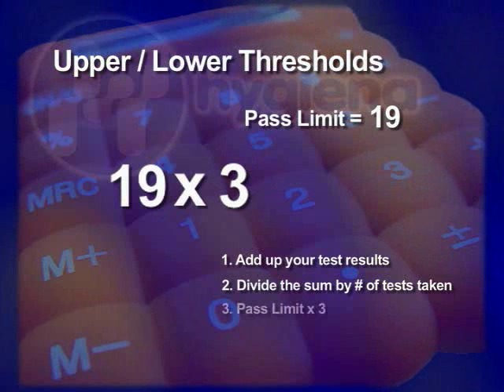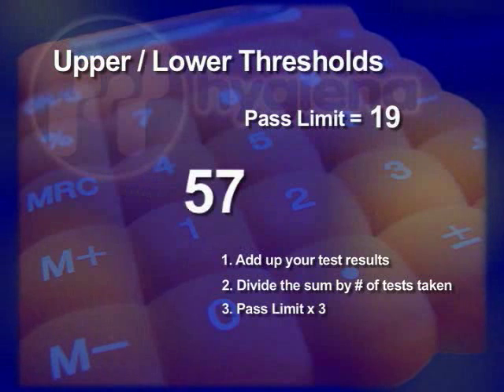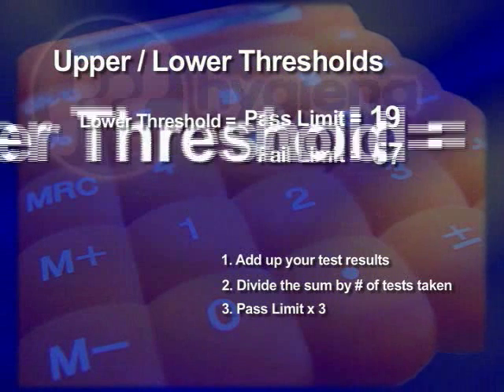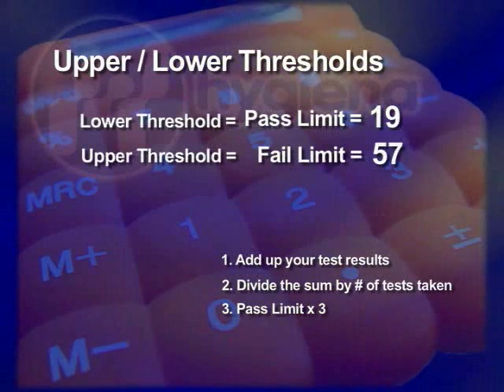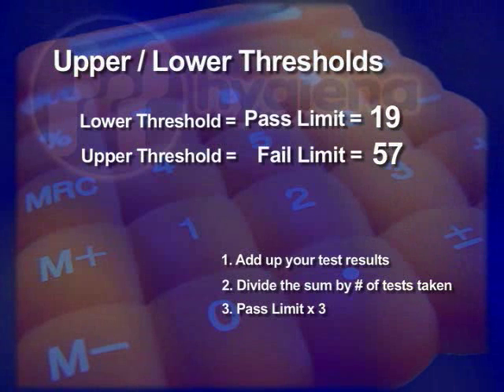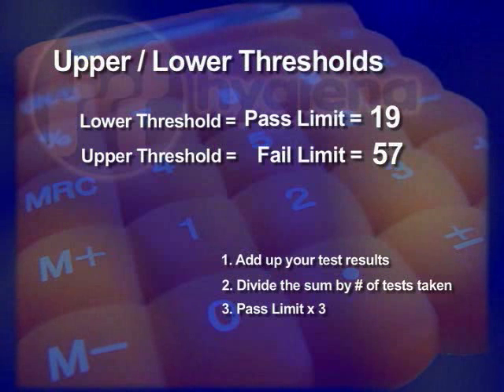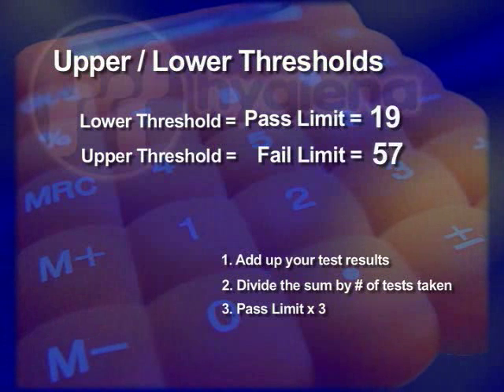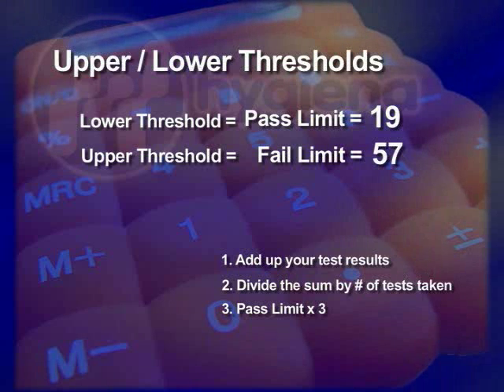Next, multiply your pass limit by 3. This will give you your fail limit. These are your thresholds. You can now enter them into your System Sure Plus program and synchronize to your device, or enter them directly into your Luminometer under the threshold category. Any test number falling in between these two numbers should be considered as a caution zone.